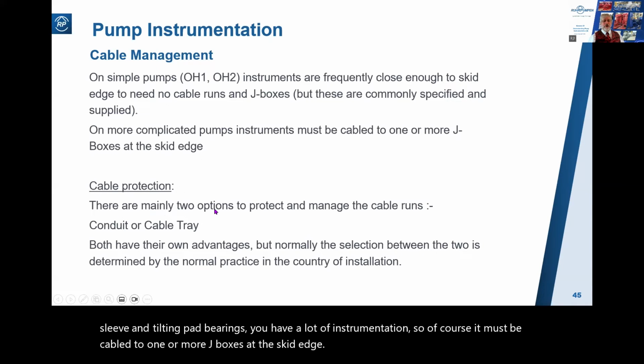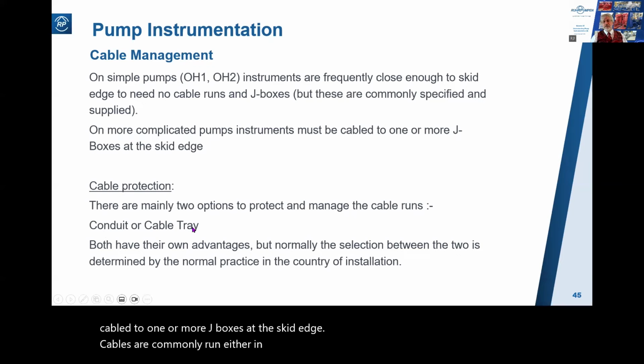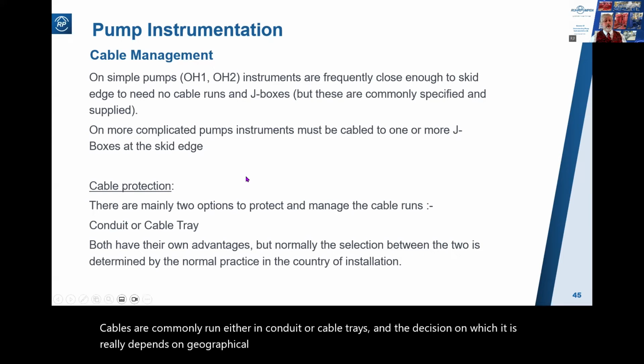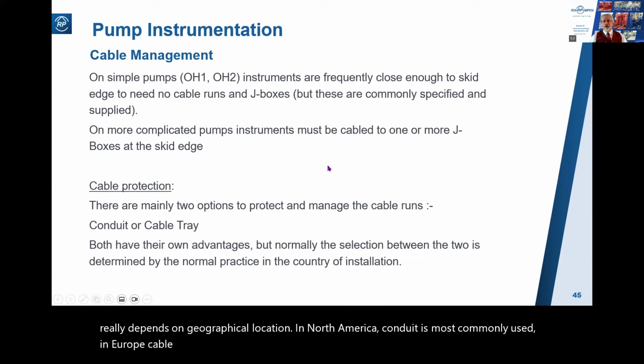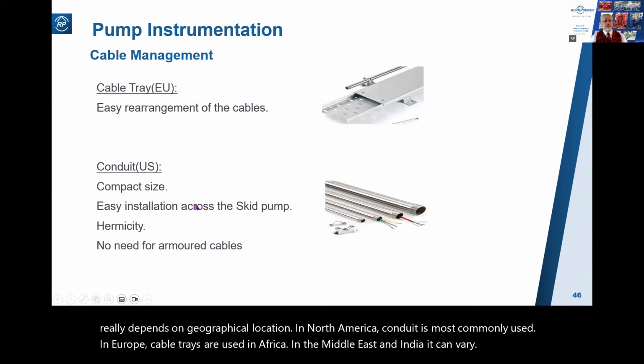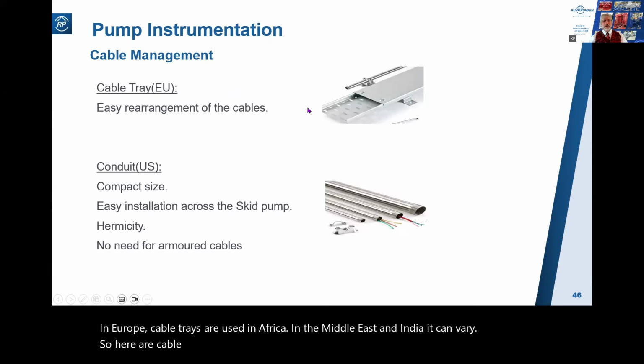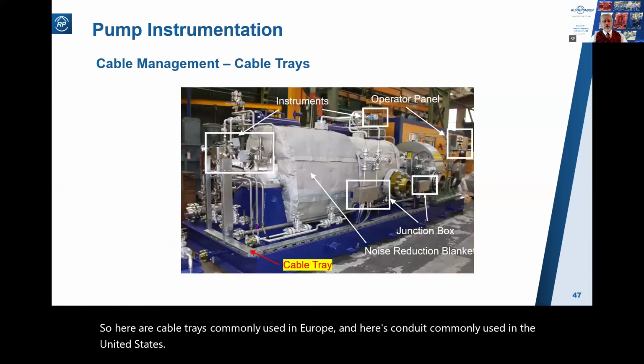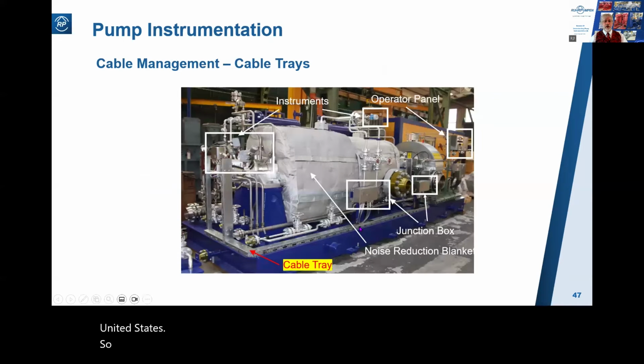Cables are commonly run either in conduit or cable trays, and the decision on which it is really depends on geographical location. In North America, conduit is most commonly used. In Europe, cable trays are used. In Africa and the Middle East and India, it can vary. So here are cable trays, commonly used in Europe, and here's conduit, commonly used in the United States. So here is a pump set with cable trays. Very neat.